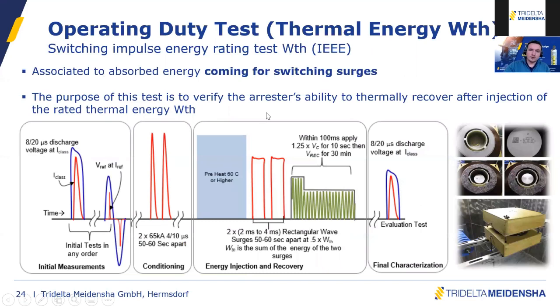You also have a typical test process here with initial measurement, preconditioning, and preheating of the blocks, because you always want to be in the worst case scenario. So here is the injection of the energy. If you need 7 kilojoule per kV rated, this is the part where we inject the energy.